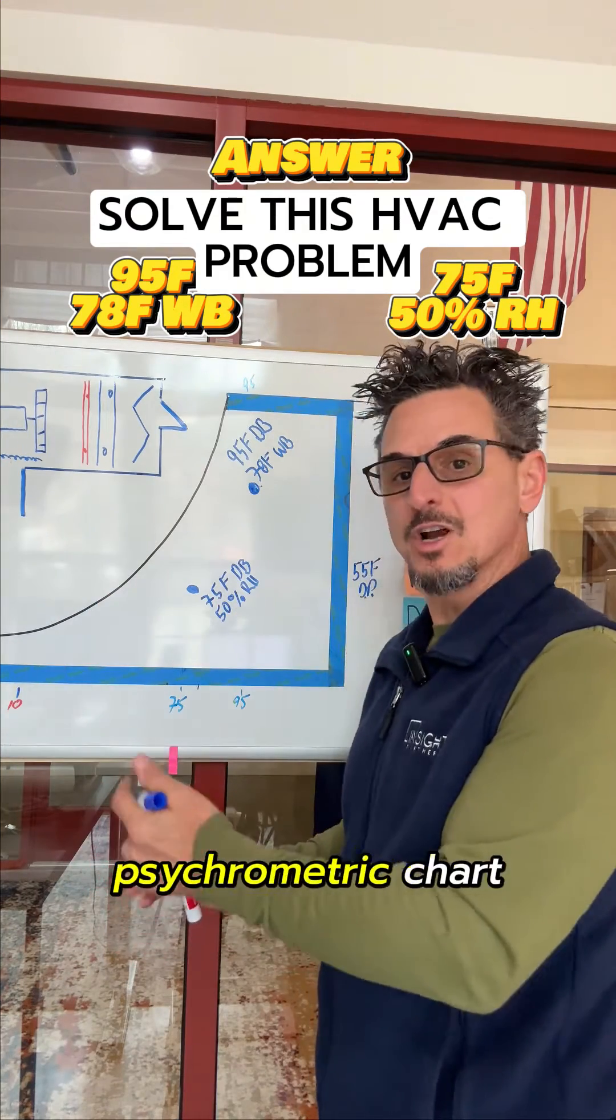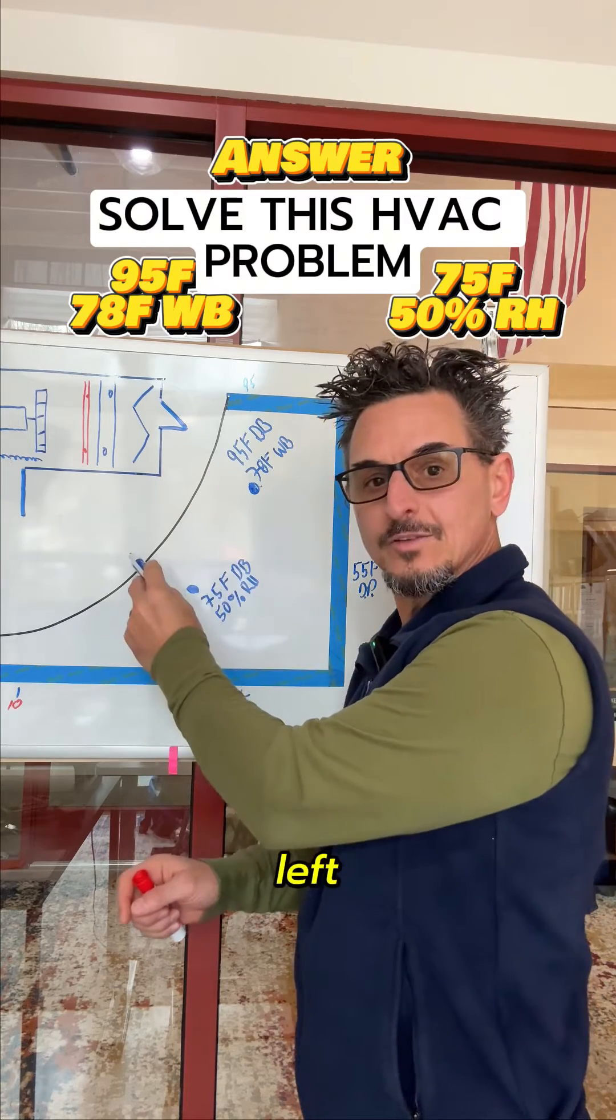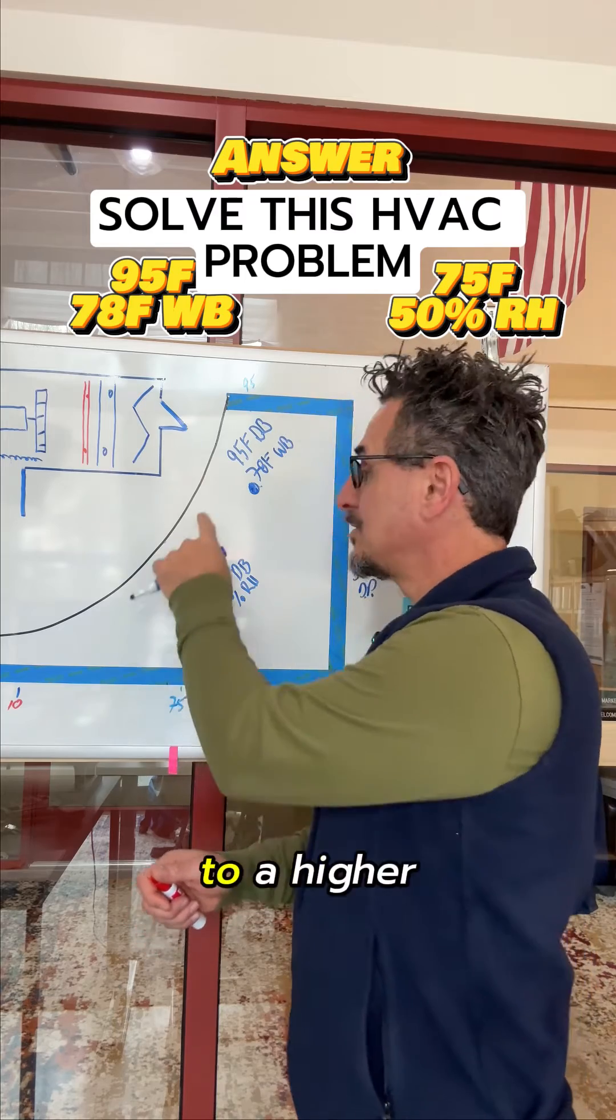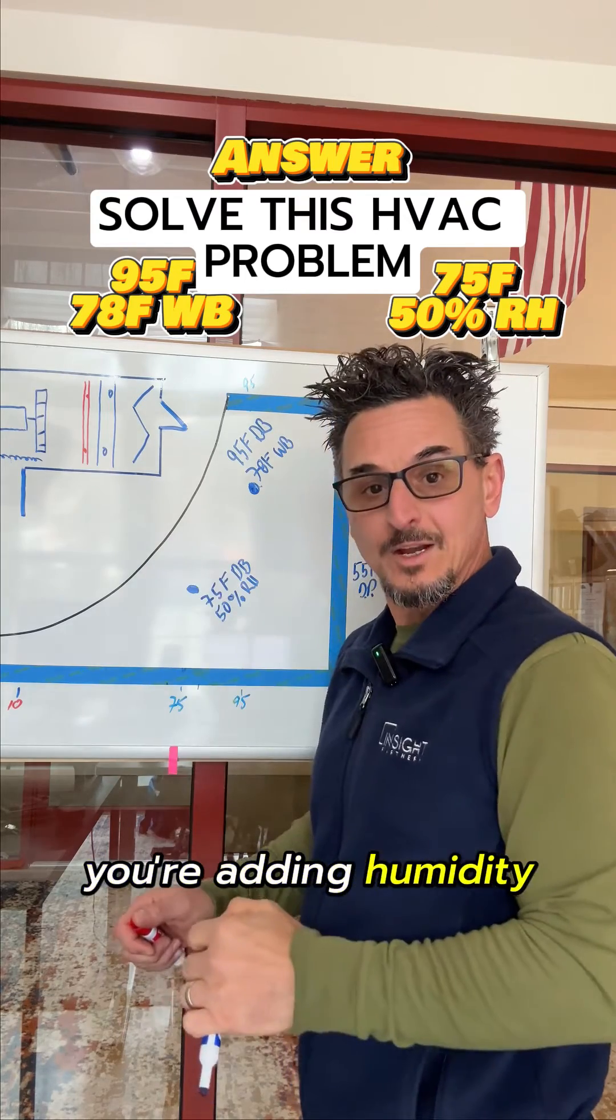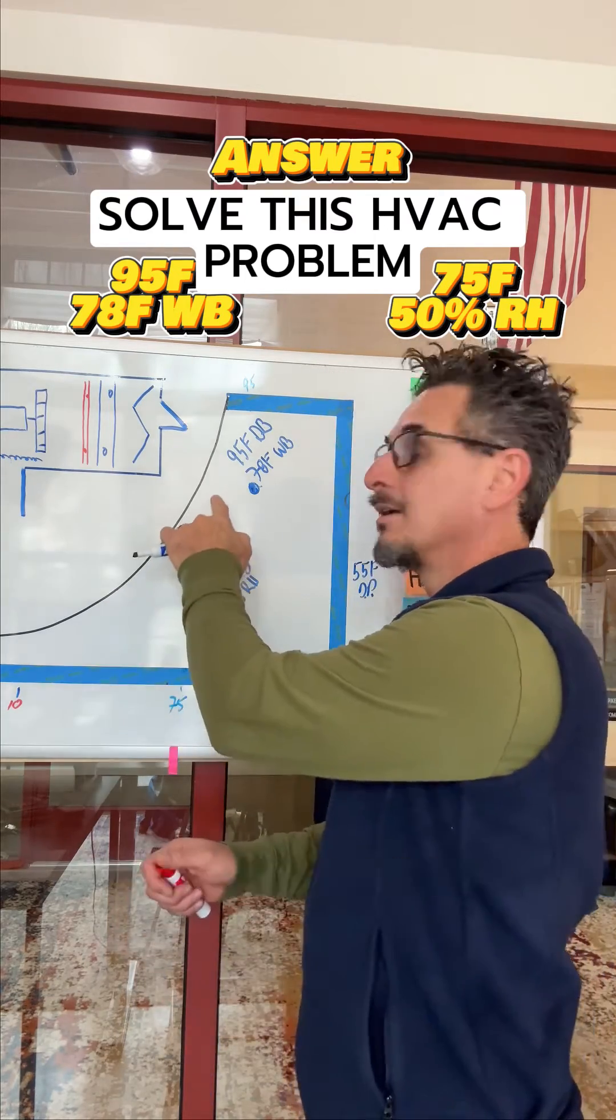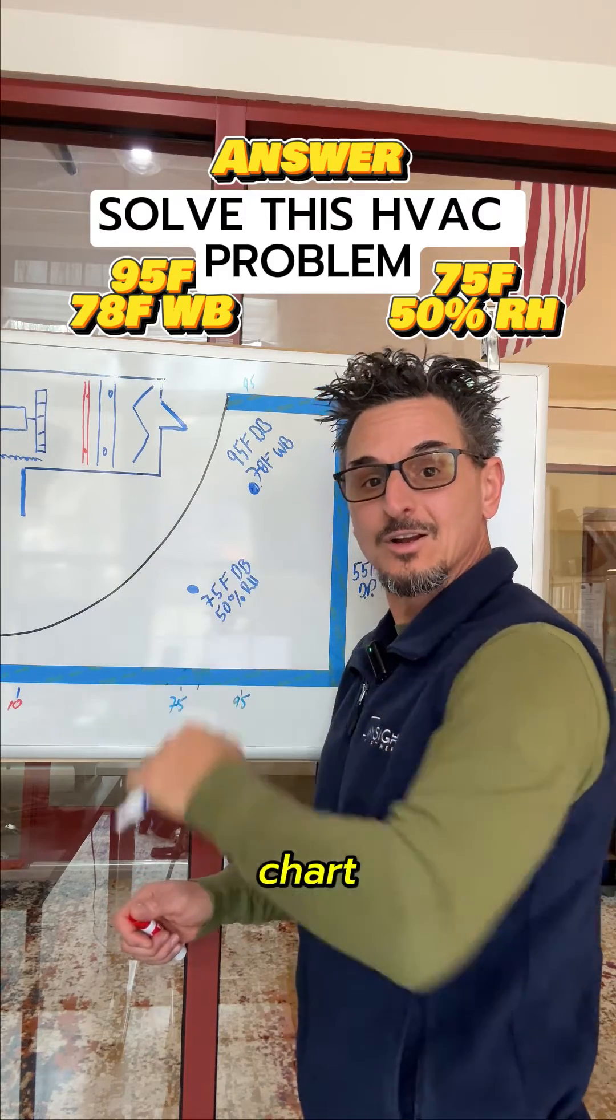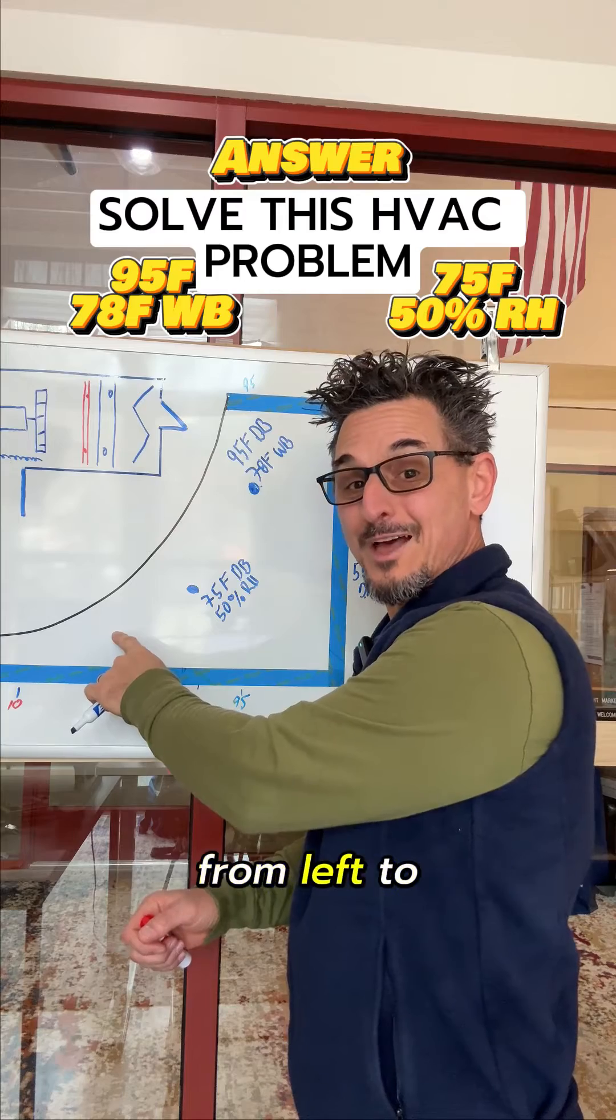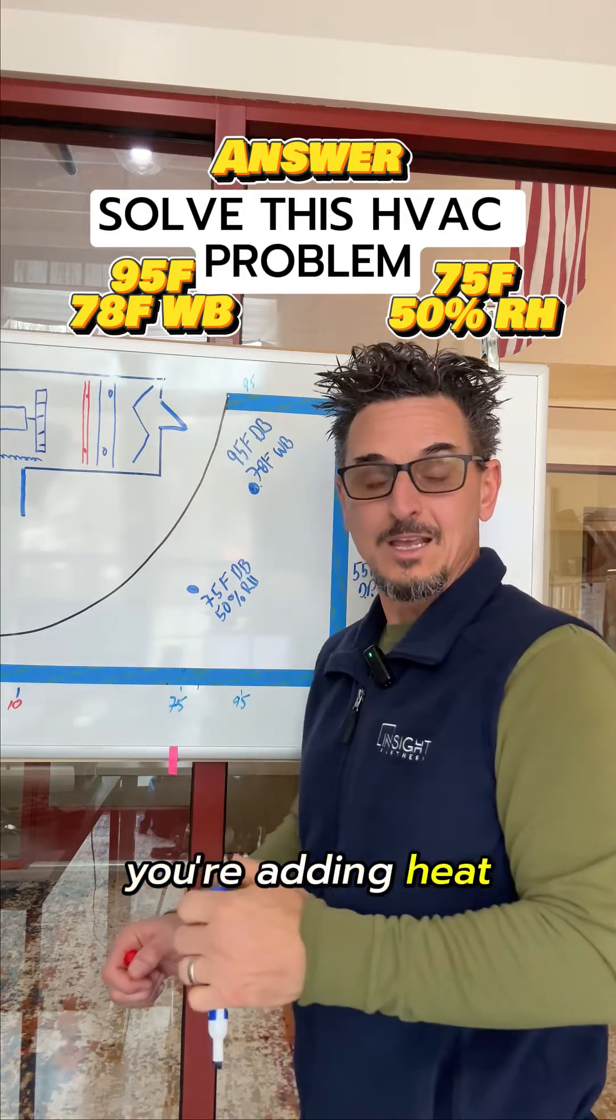So an overall view of the psychrometric chart: when you're moving from right to left, you're sensibly cooling. When you're moving from a lower point to a higher point, you're adding humidity. When you're moving down the psych chart, you're removing humidity or dehumidifying. When you're moving from left to right, you're adding heat or heating the air.